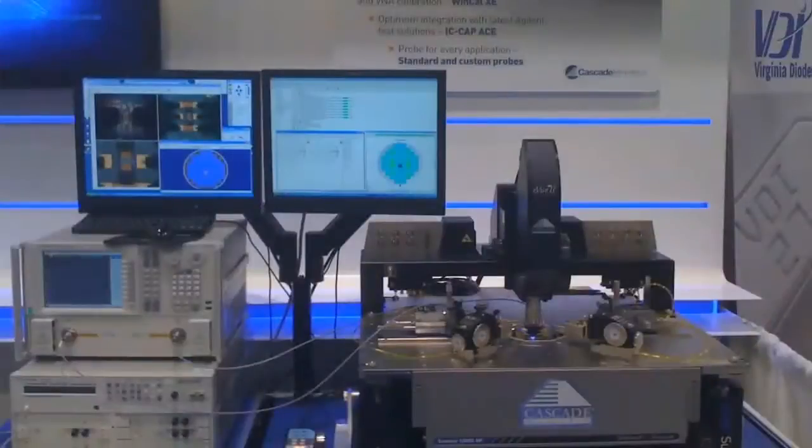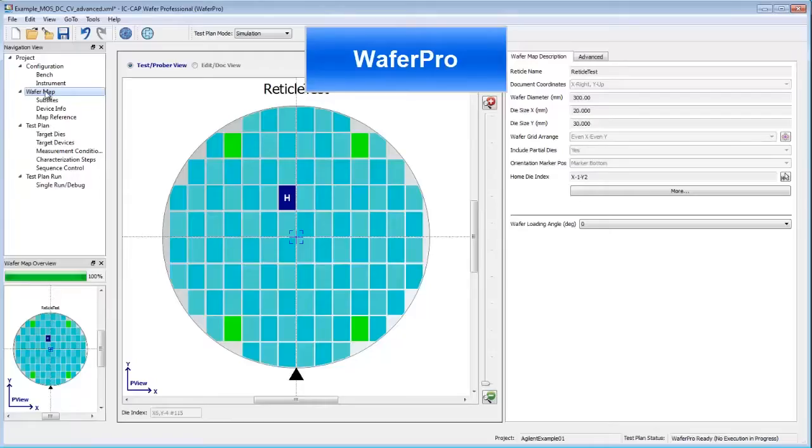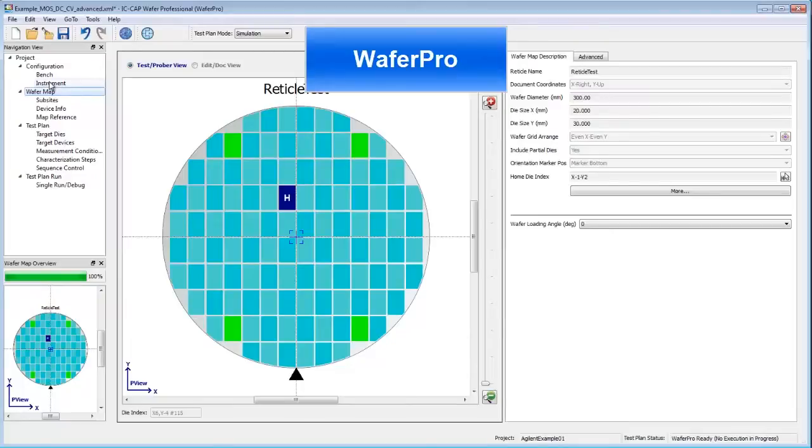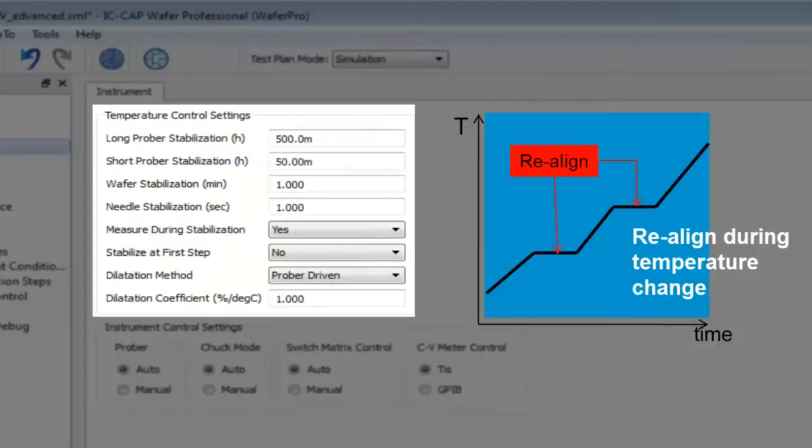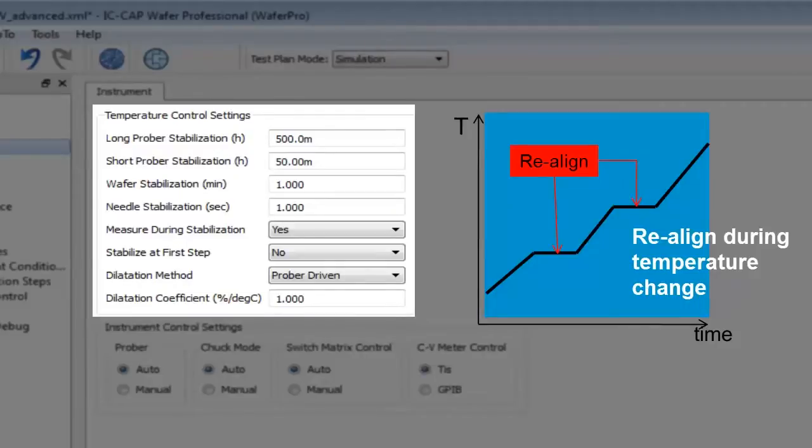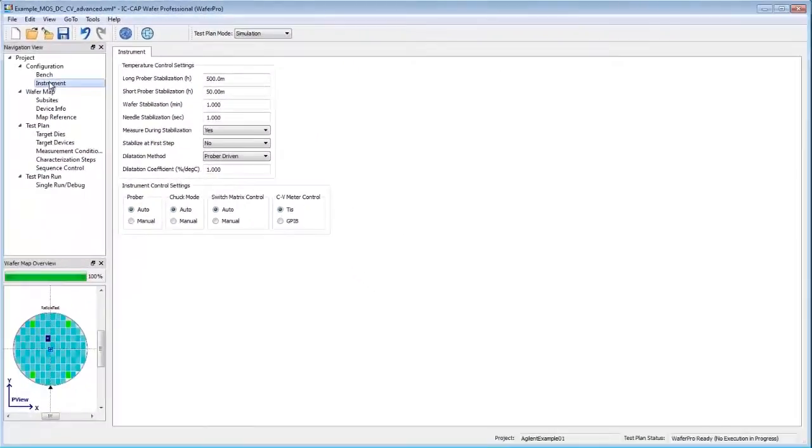One of the major challenges today is performing automated measurements across temperature. Agilent's IC-CAP WaferPro software is a fast, single, and multi-wafer automated measurement solution. It handles wafer realignment automatically at each temperature change, removing the need for engineers to supervise measurements.